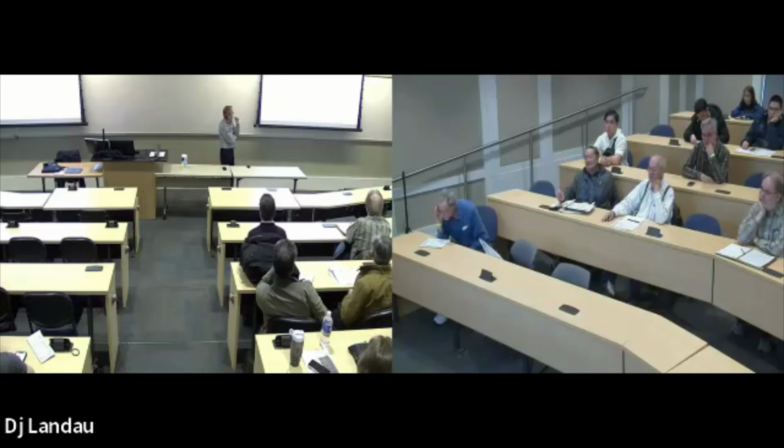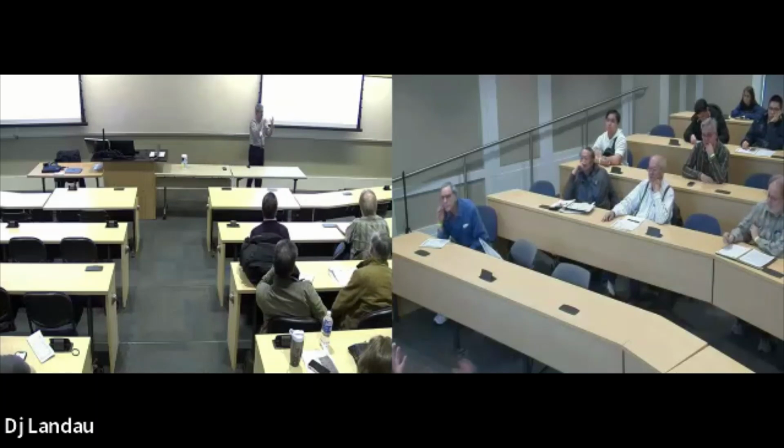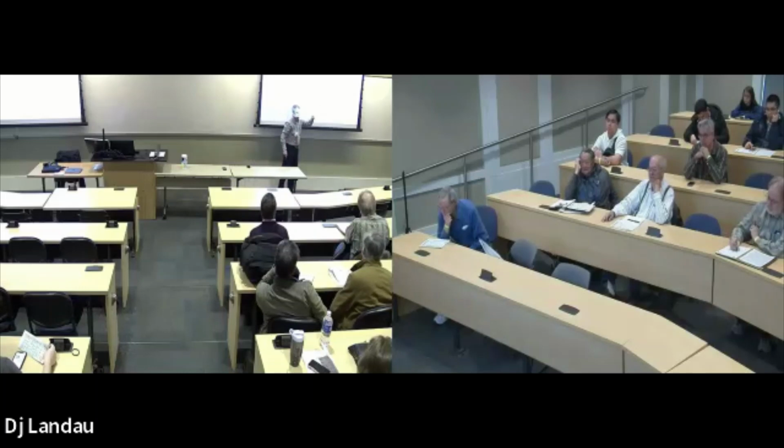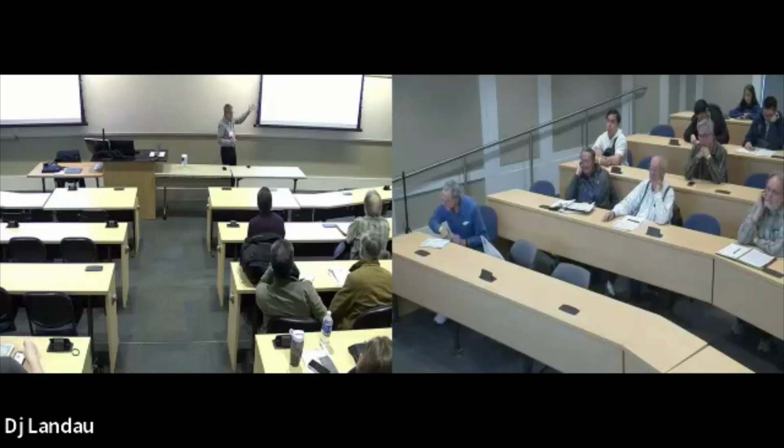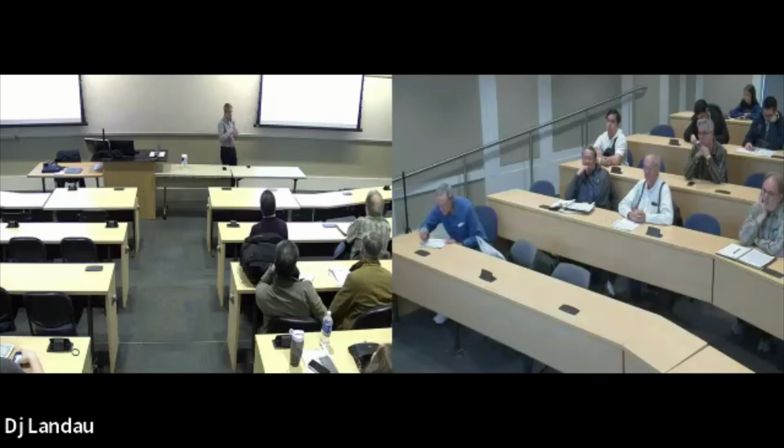Right, excellent. So this is called N-1. In other words, you have the number of elements in the system it needs to be able to survive without a blackout with N-1. So this is the -1, right? Thank you for asking that question. Now, there is an N-2 criteria that says, if you really want to build it robust, then you should be able to withstand the loss of at least 2 elements. I don't know that this system would be able to do that, but if we connect this to other utilities, then you might see where that is going to work. But N-1 is the criteria. So when I say loss, the failure of a generator or transmission line would not cause a blackout.